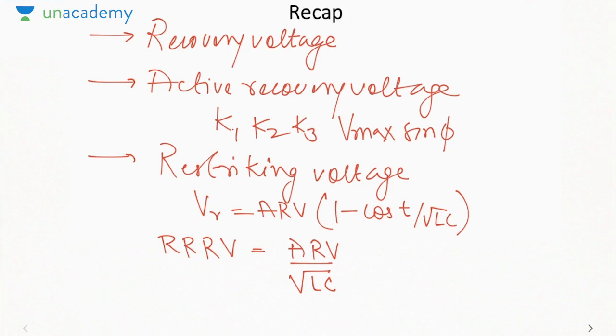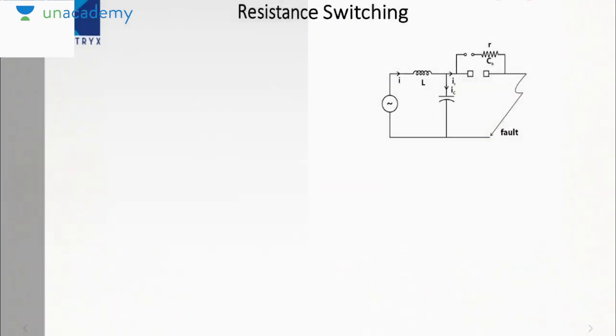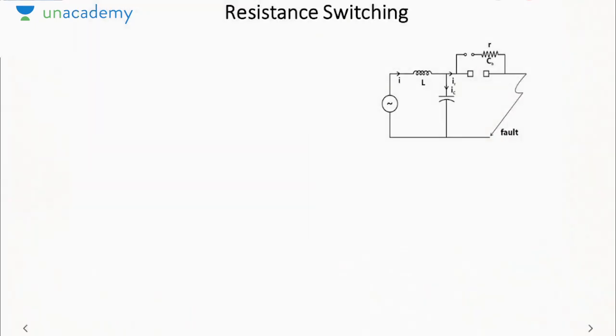Now our objective is to reduce these oscillations that are occurring due to restriking voltage, or reduce this high frequency oscillation. Now whenever you want to damp out any sort of oscillations in the electrical domain, you have to use a resistance. So next we will consider the resistance switching. So here what we do is, across the circuit breaker plates we will connect a resistance.